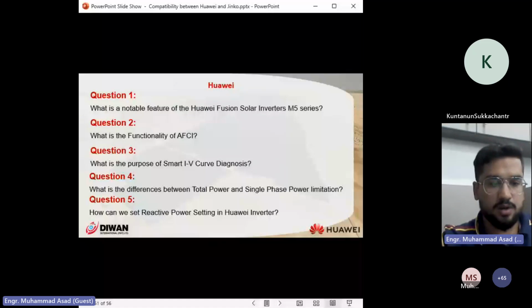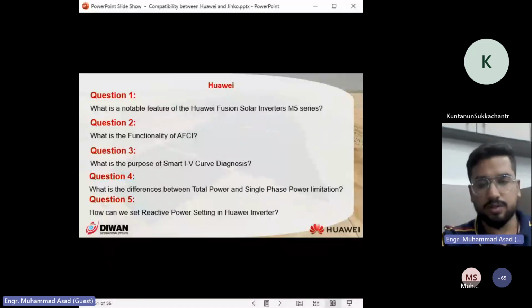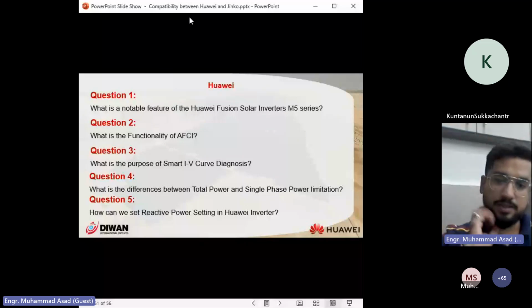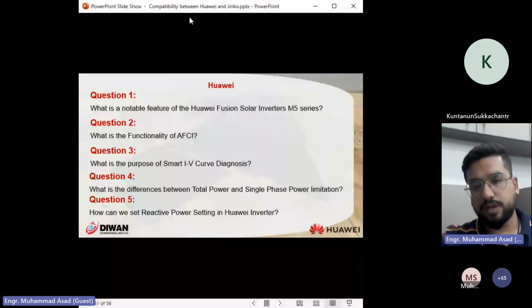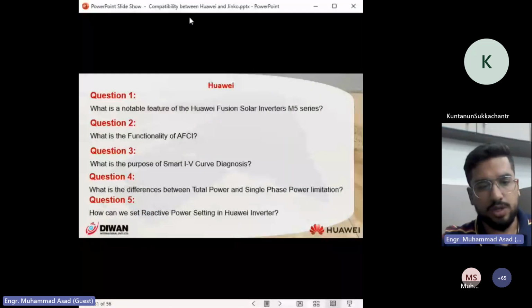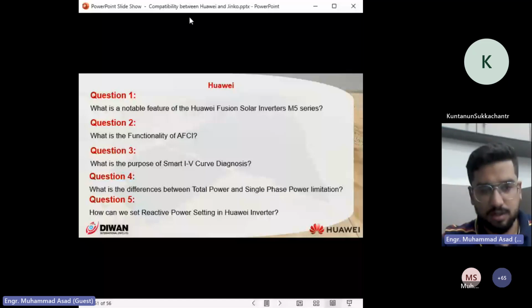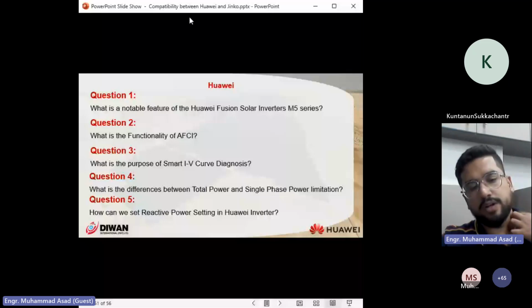The last question is, how can we set reactive power settings in Huawei inverters? As we know, since January 2023, K-Electric and other discos in Pakistan have implemented that inverters should have reactive power settings to counter the over voltage issue. By setting reactive power, we can adjust the voltages of the inverter limited to the grid level, as the grid runs with a 410 volt line-to-line difference.